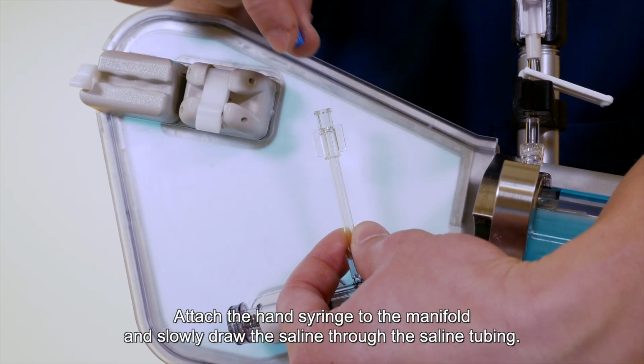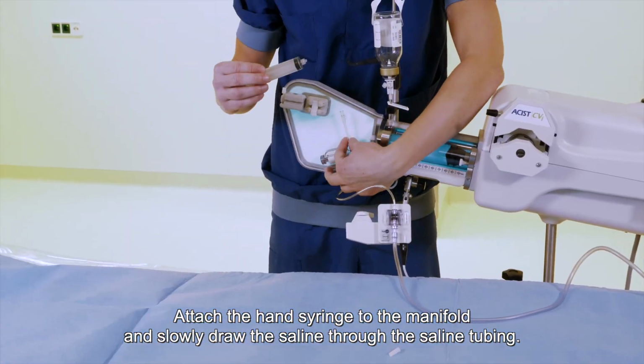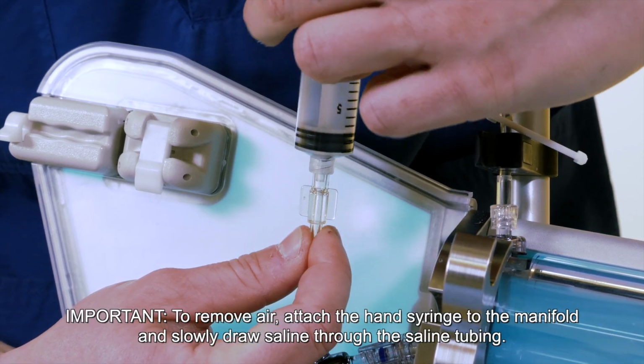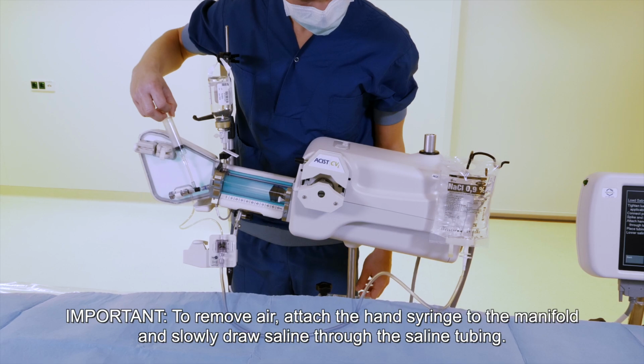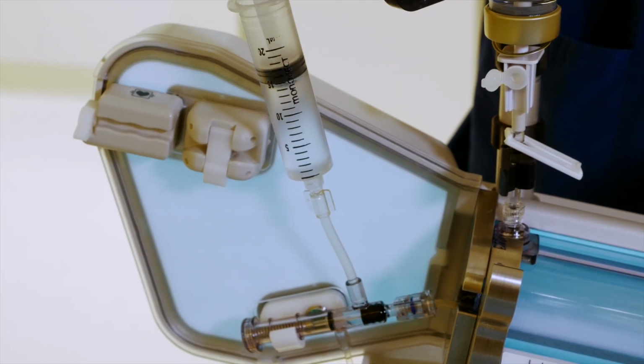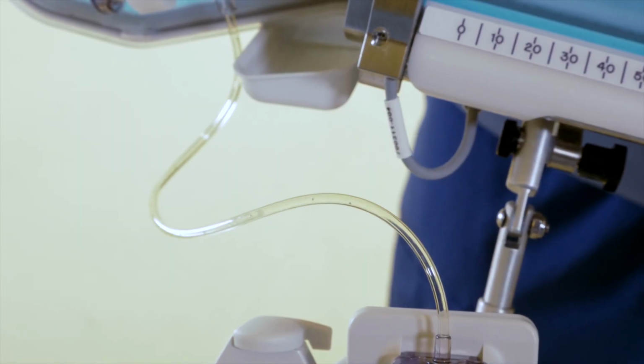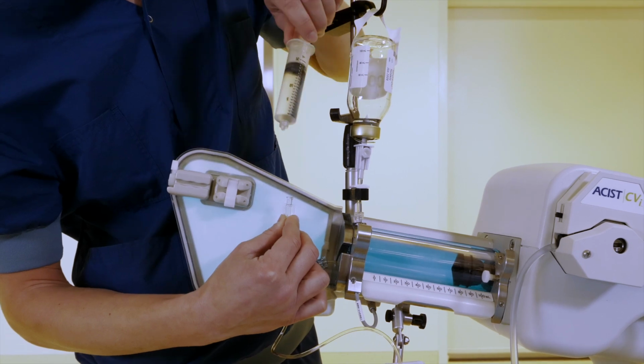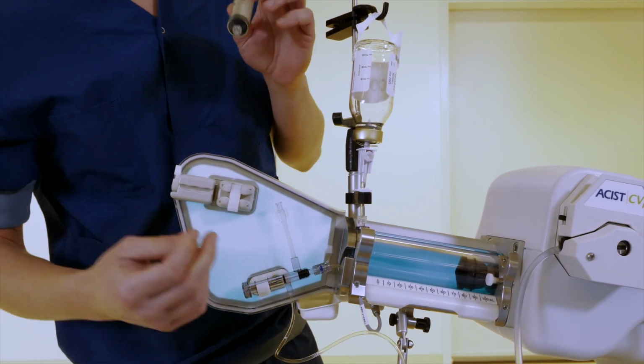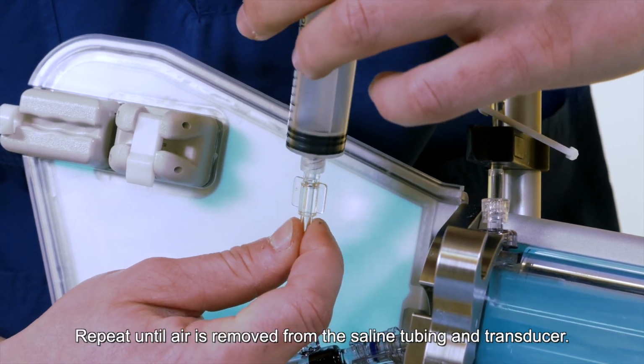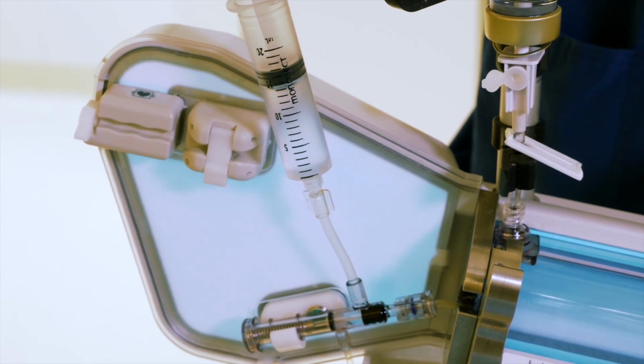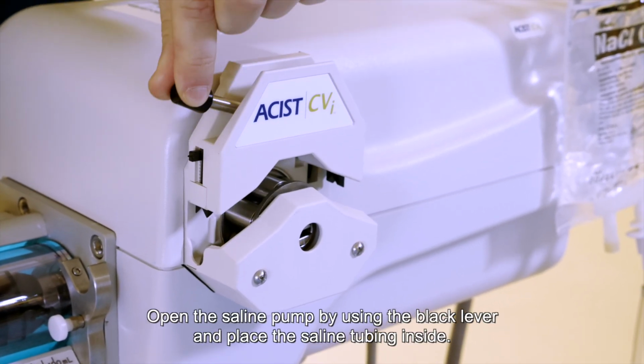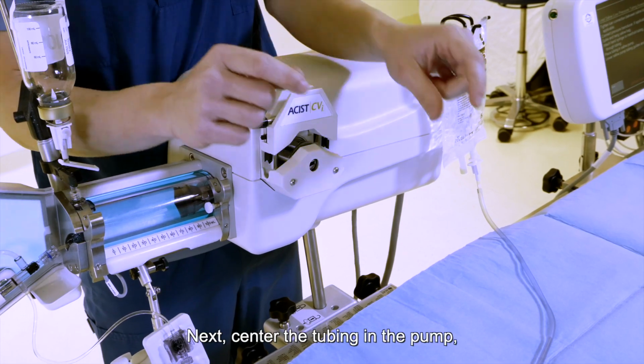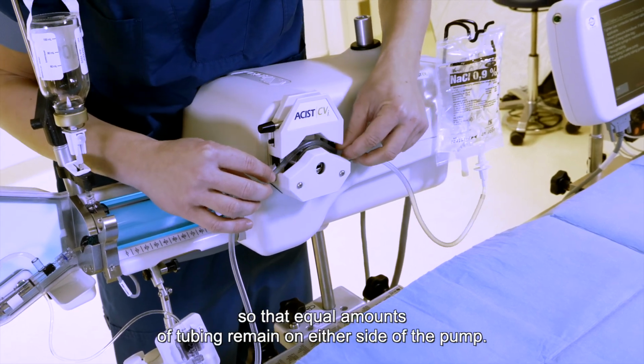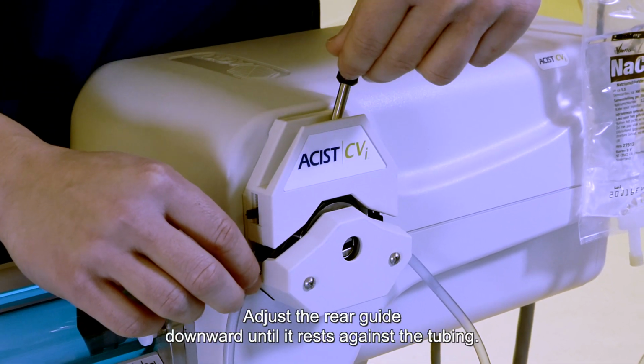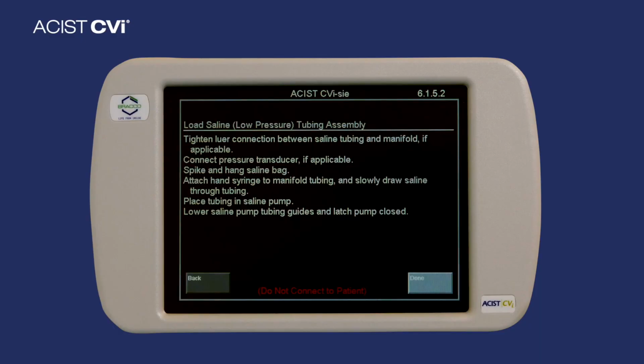Step 3. Attach the hand syringe to the manifold and slowly draw the saline through the saline tubing. Important: to remove air, attach the hand syringe to the manifold and slowly draw saline through the saline tubing. Repeat until air is removed from the saline tubing and transducer. Step 4. Open the saline pump by using the black lever and place the saline tubing inside. Next, center the tubing in the pump so that equal amounts of tubing remain on either side of the pump. Close the pump latch. Adjust the rear guide downward until it rests against the tubing. Press Done.